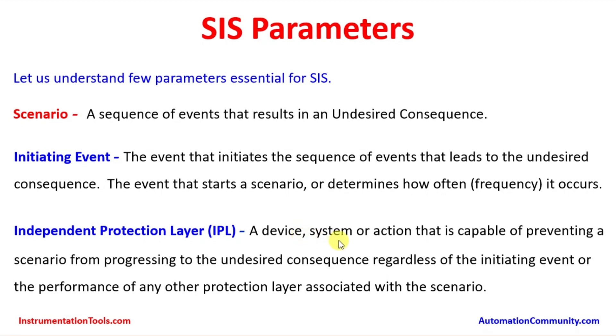An Independent Protection Layer is a device, system, or action capable of preventing a scenario from progressing to the undesired consequence, regardless of the initiating event or the performance of any other protection layer. There are multiple protection layers in a process plant: the BPCS system and operator action, alarm, safety instrumented system, pressure relief valve, rupture disc, mechanical safety devices, plant dykes, and community alarm. Each one acts independently — that is why it is called an independent protection layer.